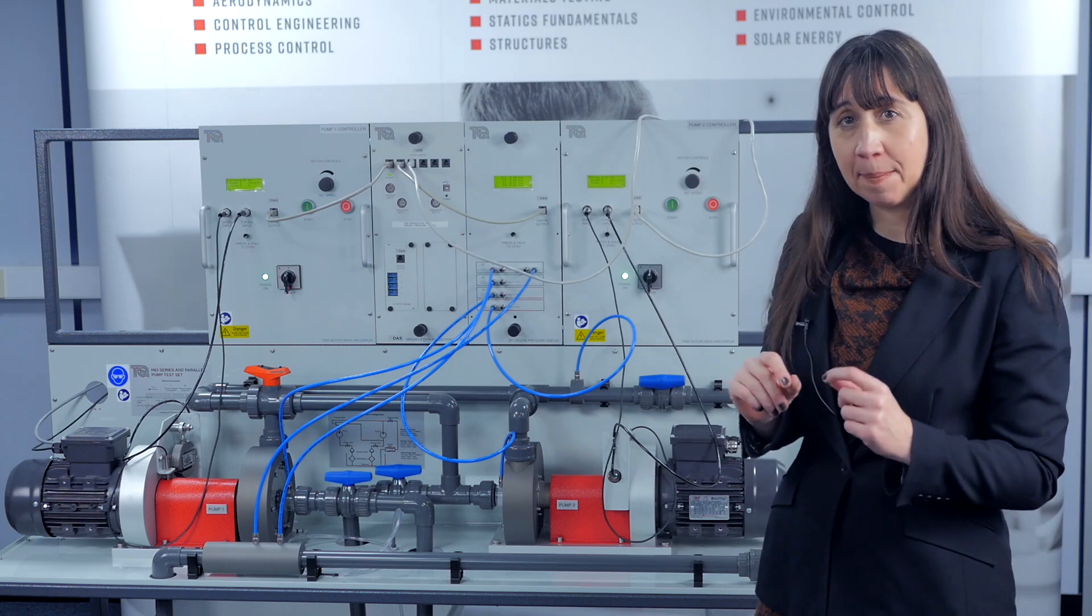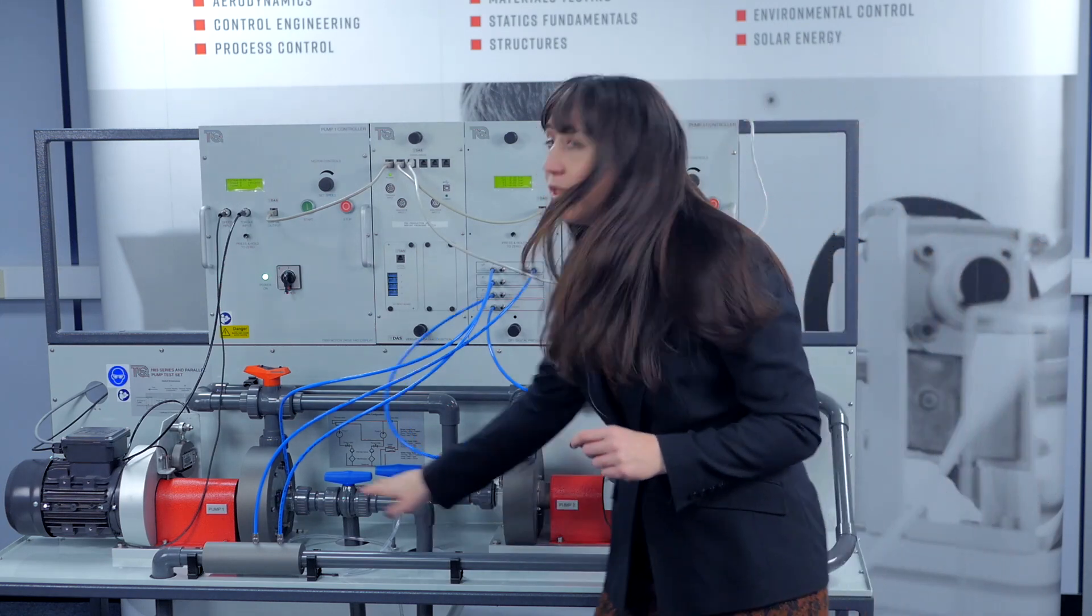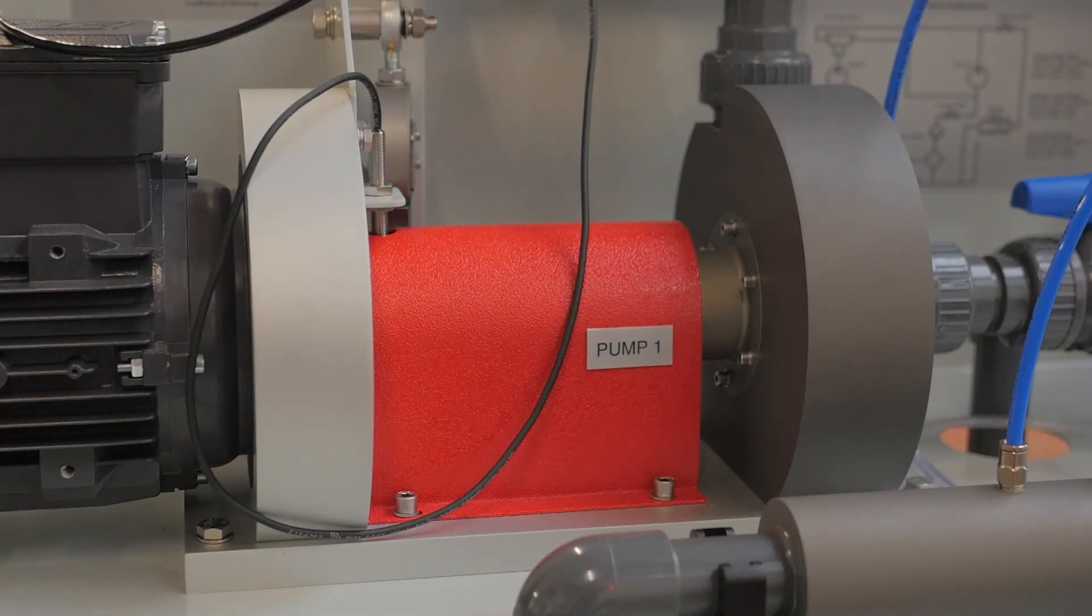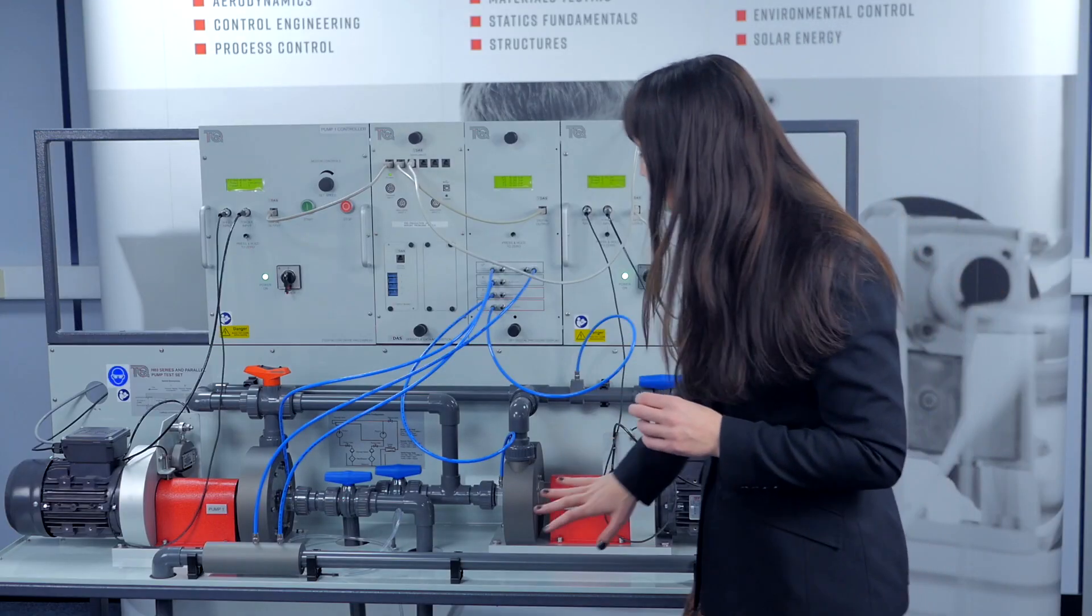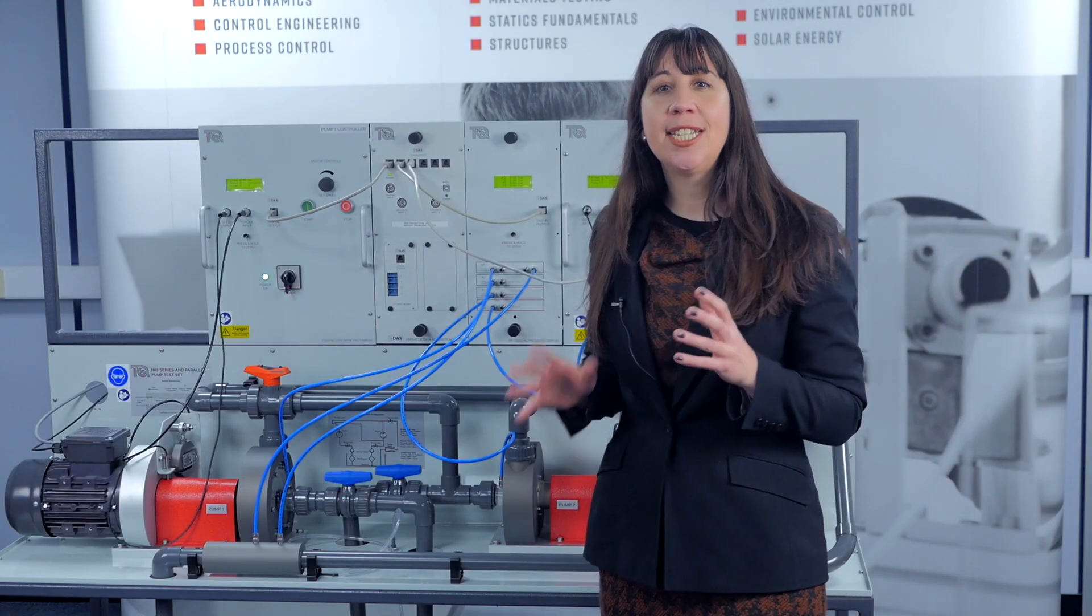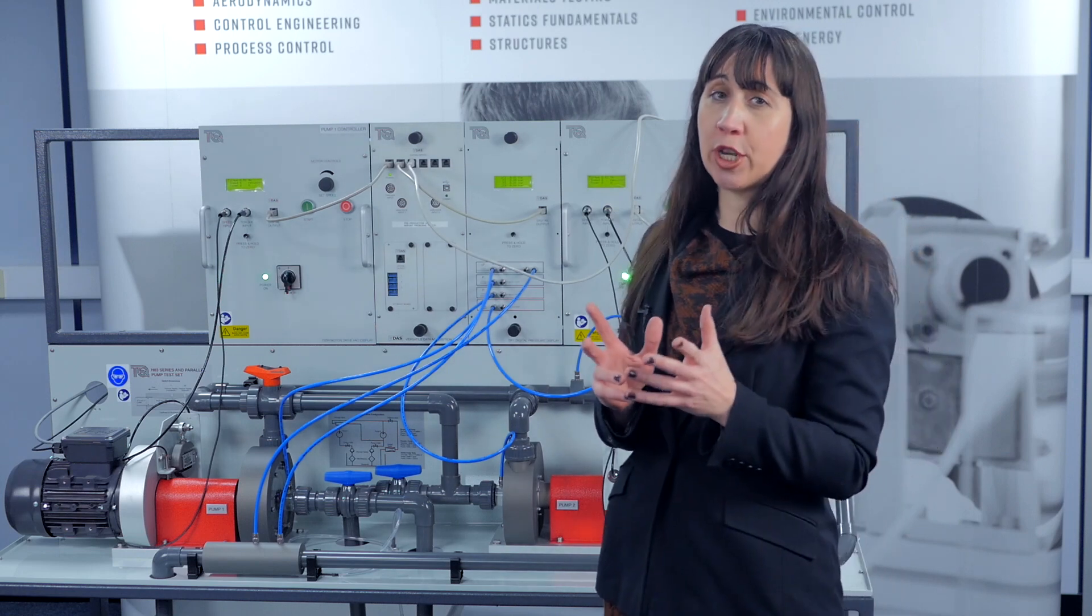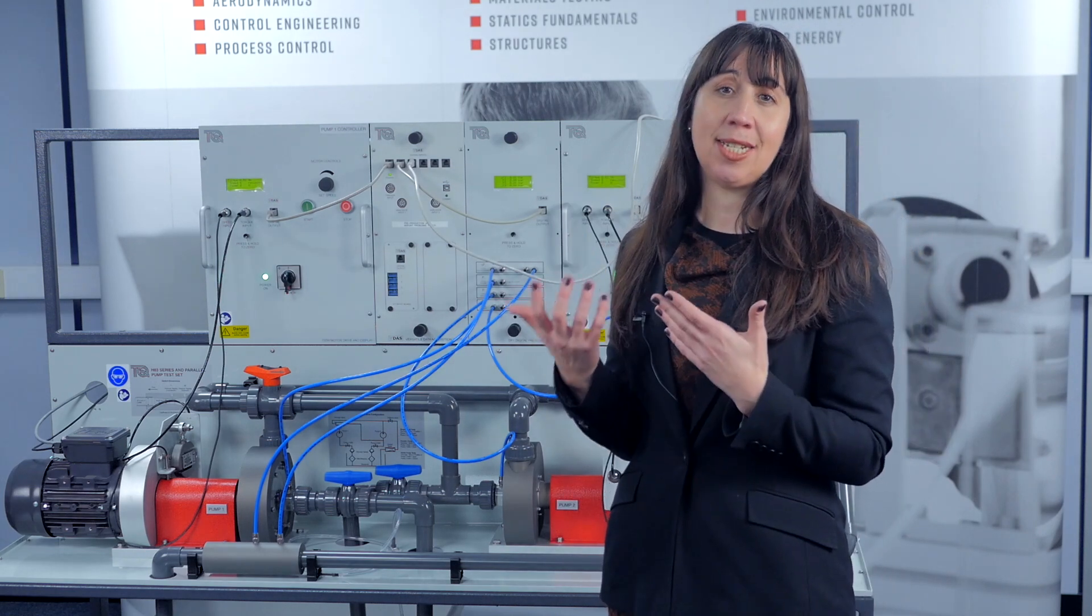Let's have a closer look at the pumps. These are both identical and you have a transparent window so you can see the impeller turning and watch how water vapor bubbles form in the pump and cavitation occurring. To see this even better, a stroboscope can be purchased to make this easier to see.